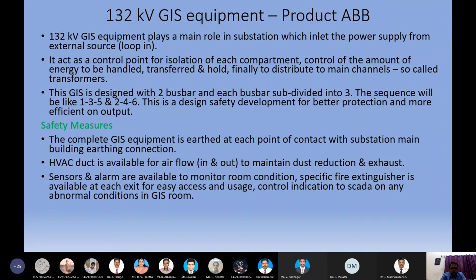Sensors and alarms are available to monitor the room conditions, along with specific fire extinguishers. Since it is an electrical substation, we have DCP (dry chemical powder) and CO2 (carbon dioxide) fire extinguishers. But these are all secondary, as a backup. The main extinguishing agent is nitrogen suppression, which we're going to see now.